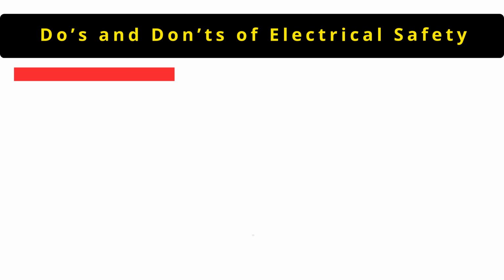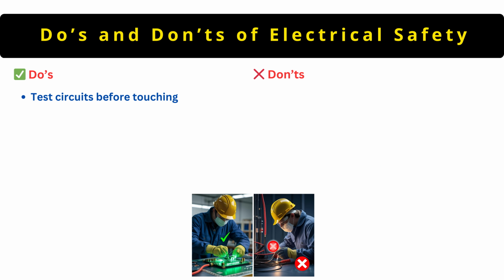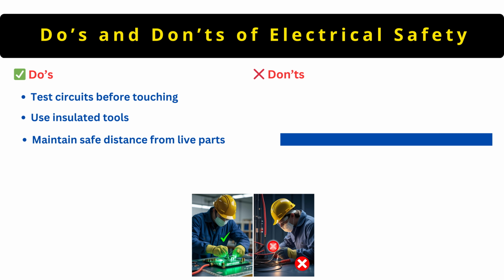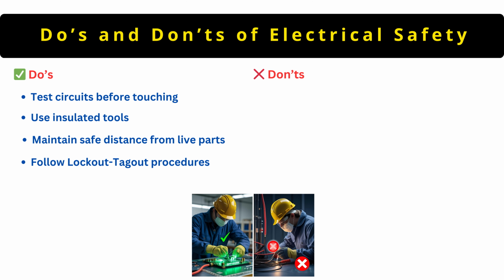Here are some critical do's and don'ts. First, test all circuits before you touch them. Use a voltage tester. Use insulated tools designed for electrical work only. Maintain a safe distance from exposed or energized parts. Always follow proper lockout tagout procedures before starting work. And report any damaged wires, tools, or panels immediately.